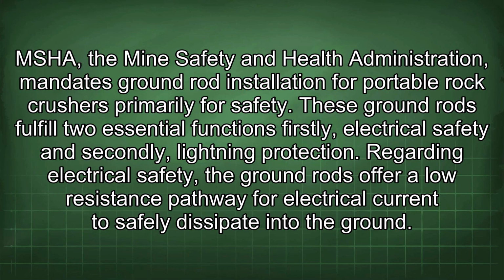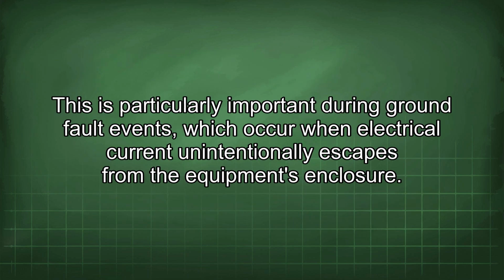MSHA, the Mine Safety and Health Administration, mandates ground rod installation for portable rock crushers primarily for safety. These ground rods fulfill two essential functions: firstly, electrical safety, and secondly, lightning protection. Regarding electrical safety, the ground rods offer a low-resistance pathway for electrical current to safely dissipate into the ground. This is particularly important during ground fault events, which occur when electrical current unintentionally escapes from the equipment's enclosure.